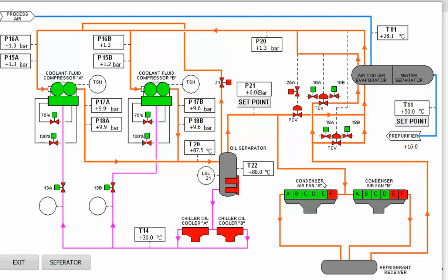While testing the air condensers, I can also tell you more about the air coolers. When the temperature of the oil reaches a danger zone, air cooler A activates. If the high temperature condition persists after a timer, air cooler B also becomes active. The conditions for running the air coolers are independent of the running of the chillers.